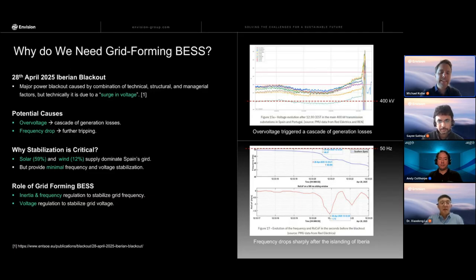And then, of course, it is important because as we move to higher penetration of renewables, in this example, 59% solar and 12% wind, so similar situations as in high windy days in the UK, obviously with a bit less share of sun, that's exactly when grid forming can help. So in the context of this event, I'm not sure grid forming BESS would have prevented the Iberian blackout, but it would have provided time, and it could have helped with the concrete symptoms of frequency decline and voltage surge and oscillations. So now, enough from me.